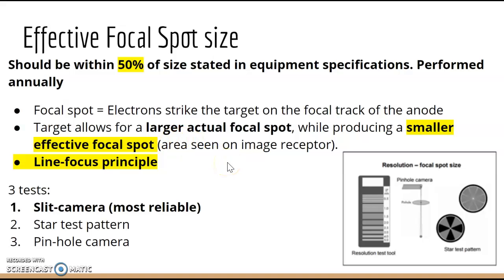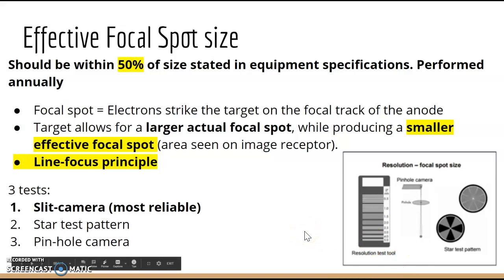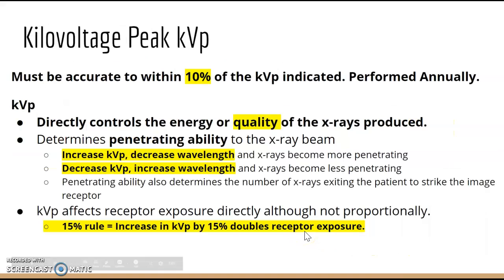The actual focal spot is larger than the effective focal spot — review the line focus principle. To test for focal spot size there are three main tests: the slit camera, which is the most reliable, the star test pattern, and the pinhole camera. For kVp, it must be accurate within 10% — meaning if you set 100 kVp on the control panel, what the tube actually produces must be within 10 kVp.